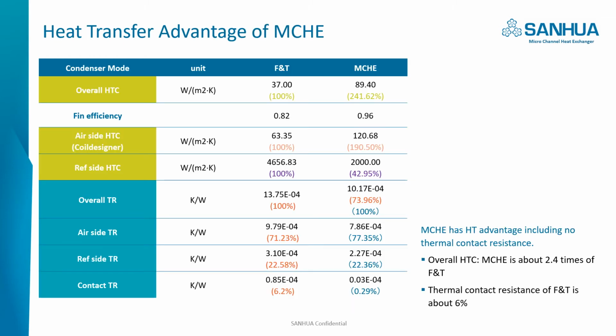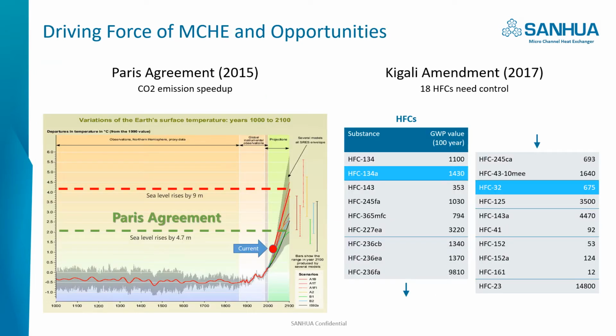This is a heat transfer model comparison of both heat exchangers. Microchannel heat exchanger has about 90 overall heat transfer coefficient, about 2.4 times of a fin and tube heat exchanger, and the air side microchannel has about 2 times of fin and tube heat exchanger coefficient, and the contact thermal resistance ratio of the fin and tube heat exchanger is about 6%, but the microchannel is almost 0. Microchannel heat exchanger has a wonderful application potential and the background of global environment policies.